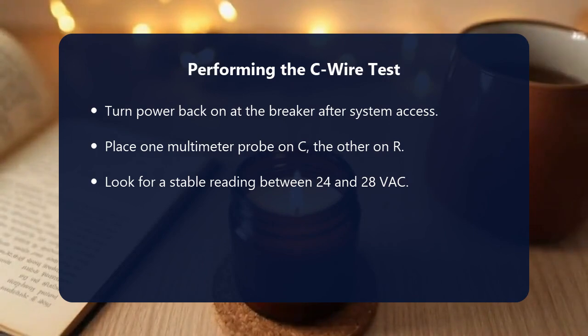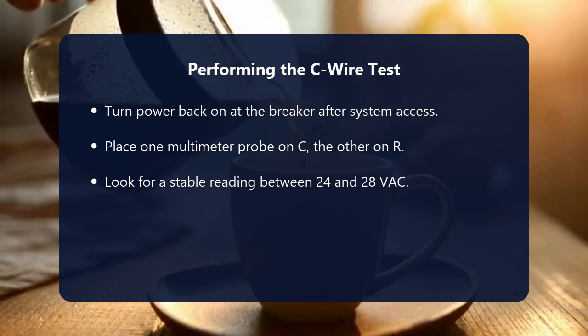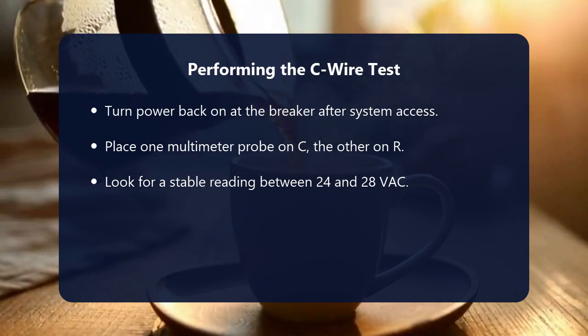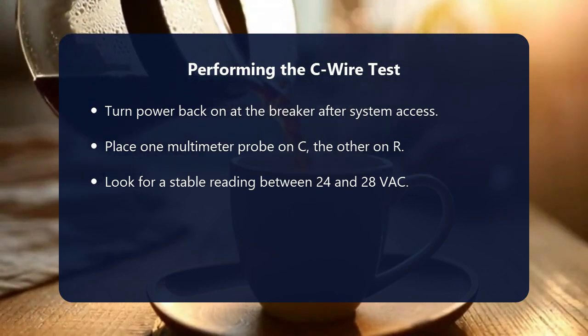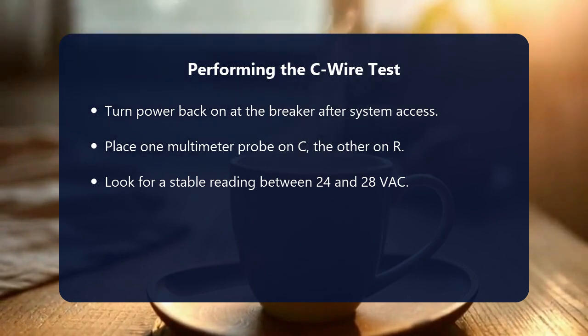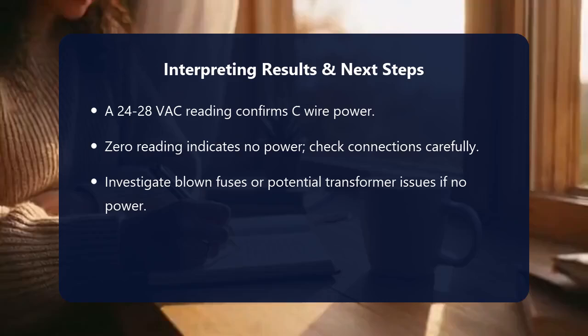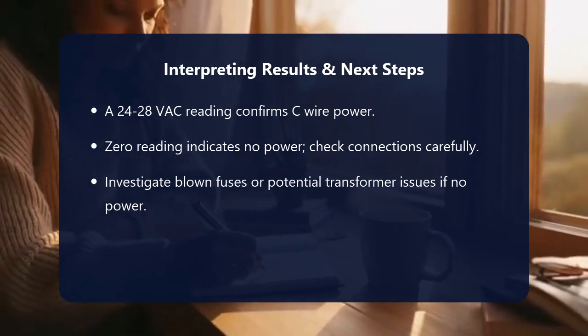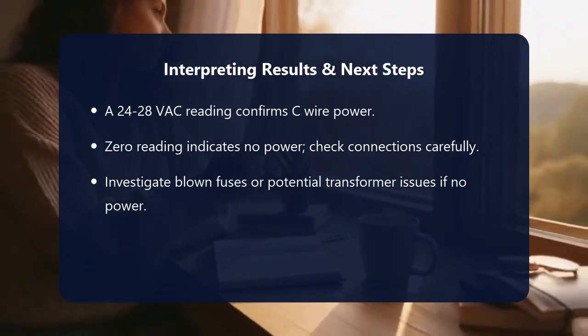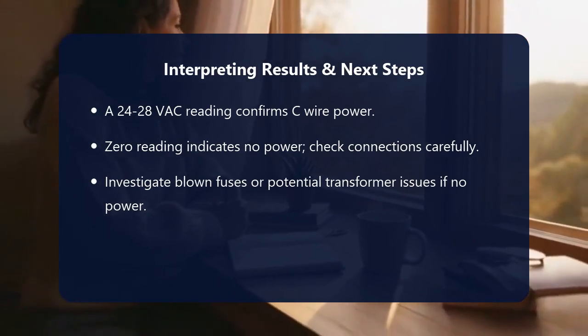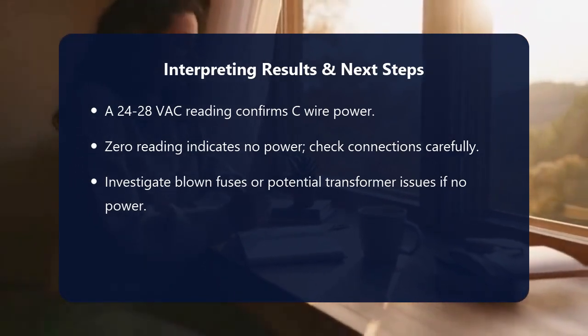If your multimeter shows 0 or a very low reading, e.g., less than 20 VAC, it means there's no power on the C-wire. In this scenario, you'll need to troubleshoot further. First, double-check that the C-wire is securely connected at both the control board and your thermostat. If applicable, a loose connection is a common culprit.